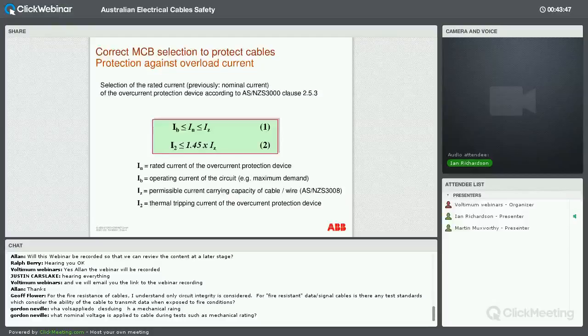So that's pretty simple. We know what current is being drawn by the load. We know the limit that the cable can actually withstand, and we have to choose a breaker which is going to protect somewhere in the middle. We've also got that second formula, where the thermal tripping current of the overcurrent protective device, and this factor of 1.45. This number comes in quite importantly in a lot of the cable designs because it is an overload factor of the cable, which you'll see on one of the next slides.